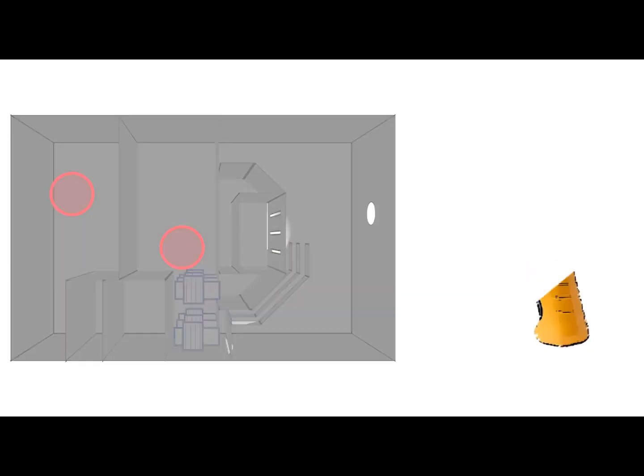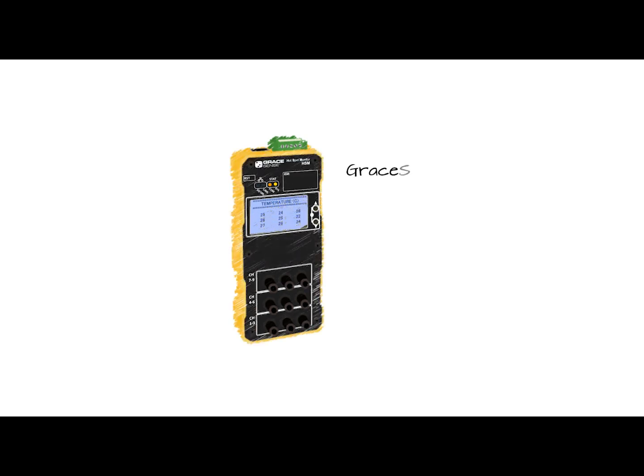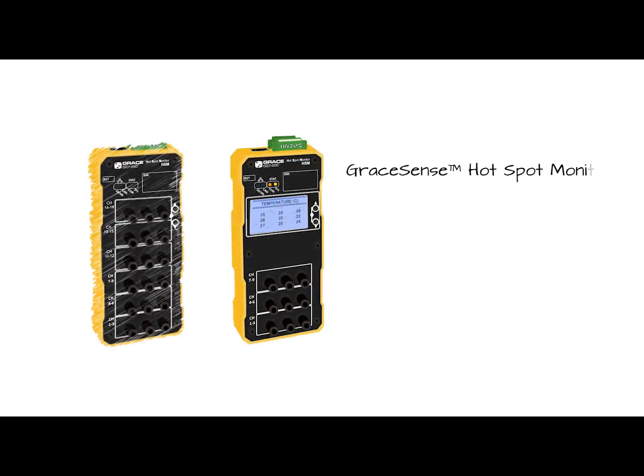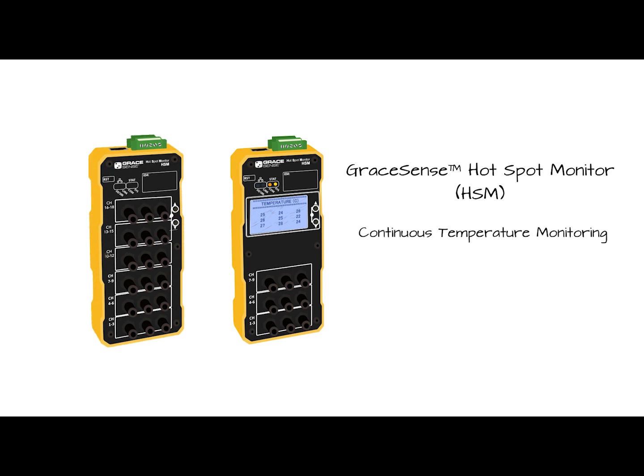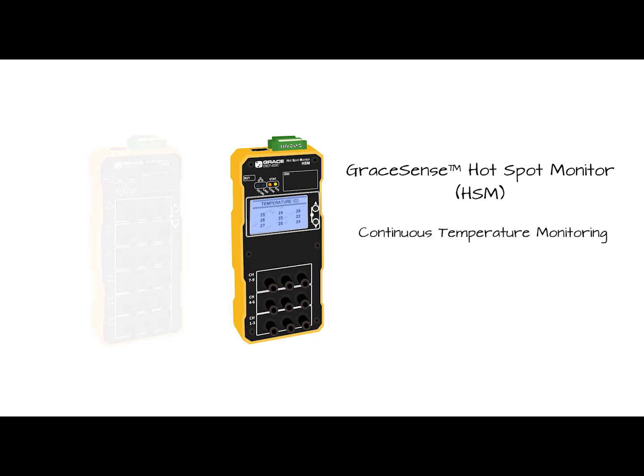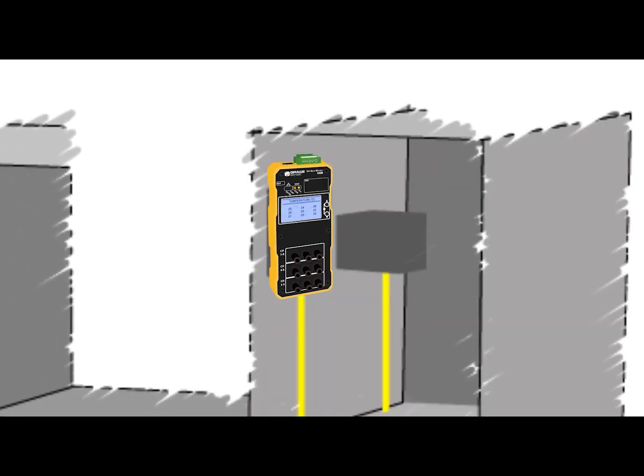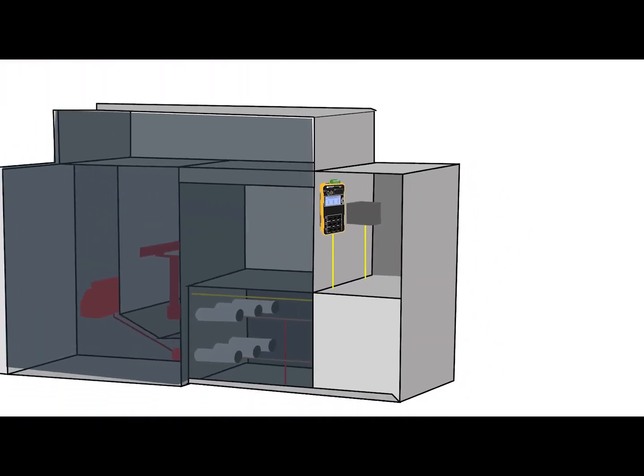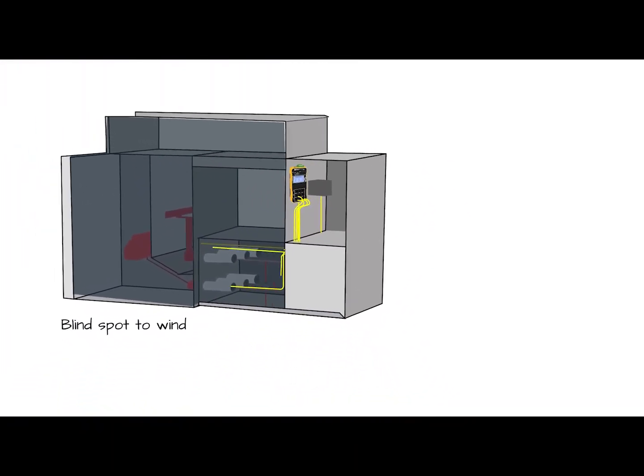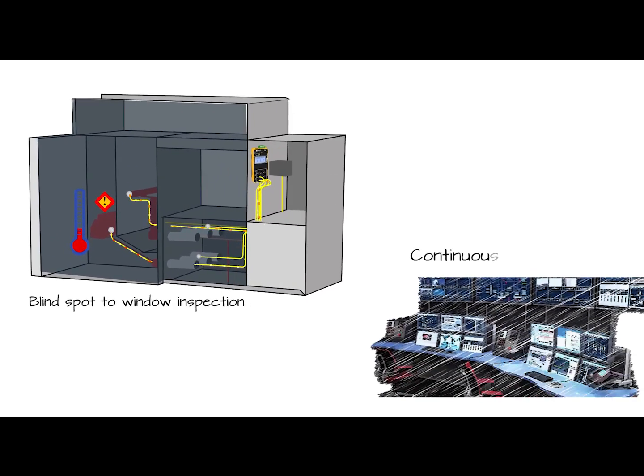of the IR window. To help you address these concerns effectively, we'd like to introduce our new GraceSense Hotspot Monitor, or HSM, a continuous real-time temperature monitoring device intended for locations that are difficult and hazardous to access. This device not only measures the temperature at any given point in time, but also proactively monitors and enables the user to predict the failure before a potential shutdown.